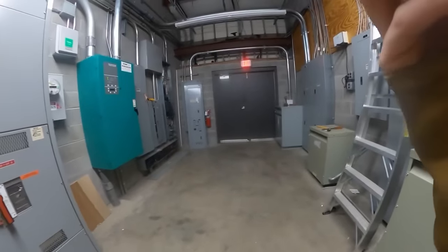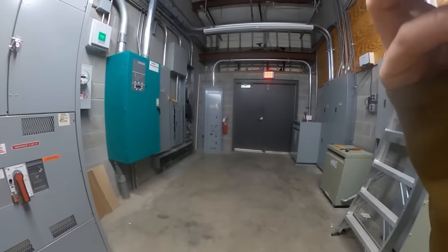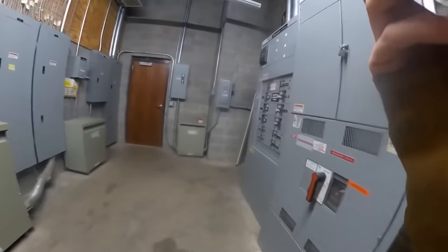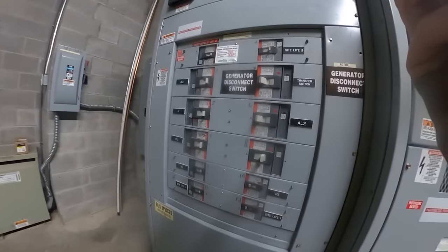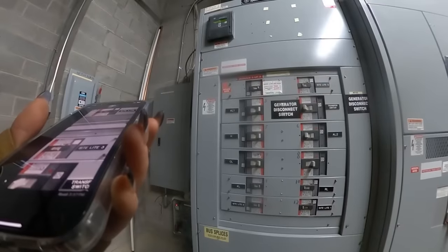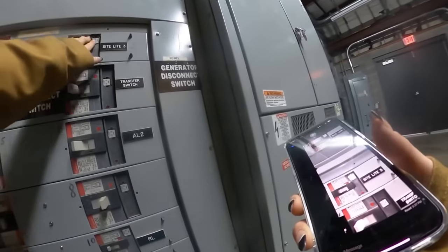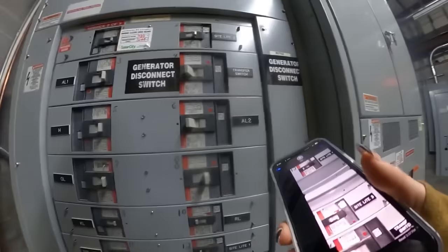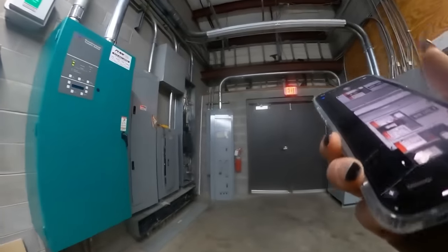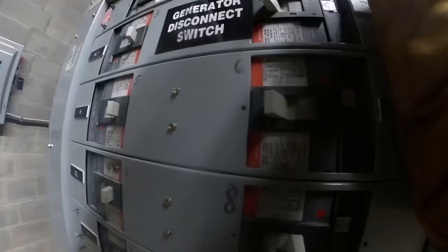I turned the main breaker off to try and tighten that lug but it's not moving — it's melted. I tried to turn the site lights back on and it's tripping immediately. The breaker isn't even kicking over into the on position now. We've got to order two breakers. They're not going to have any lights now. We've turned that breaker on and off a million times before — something's really wrong here.